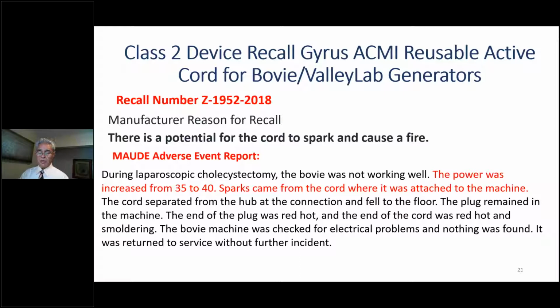But the point is, as a biomed or FDA, being a bit disappointed when we just check the machine and say it checked out okay. A better approach would be to ask why that cord failed and how many of them we have in the hospital. Maybe I need to go check for continuity and see if similar issues are happening. But in that case, it was a quick check: the machine is okay, let's put it back in use.